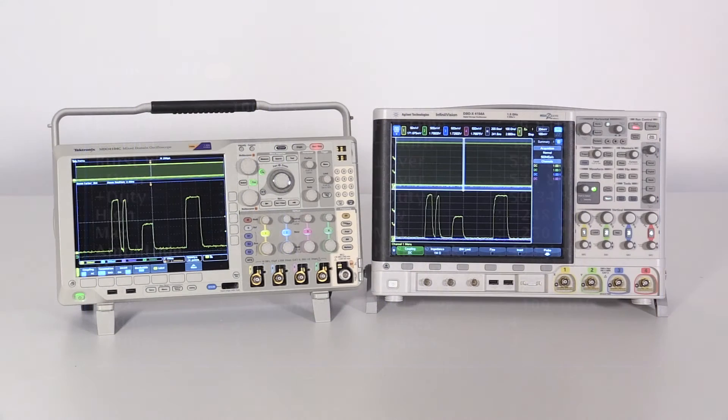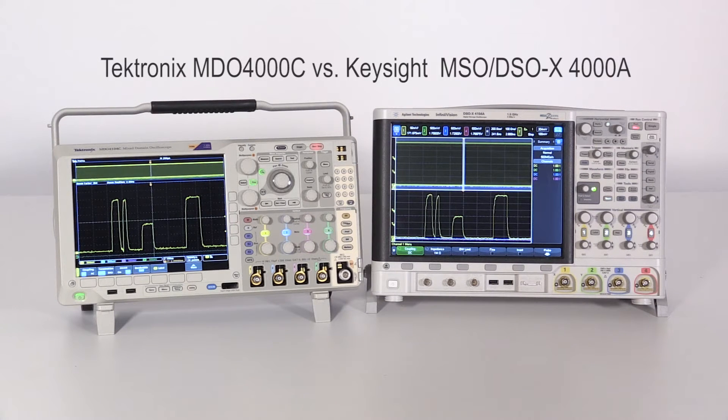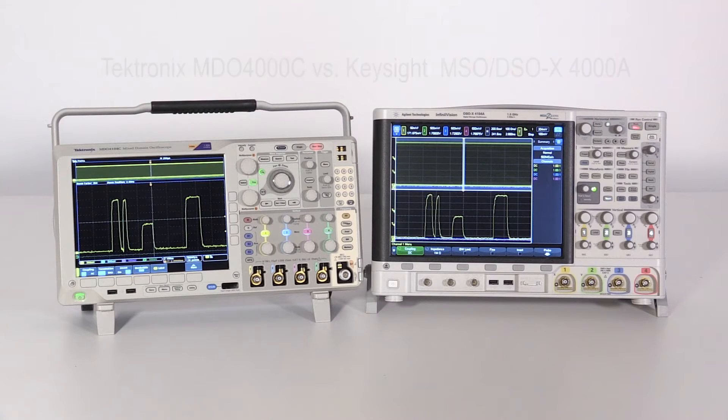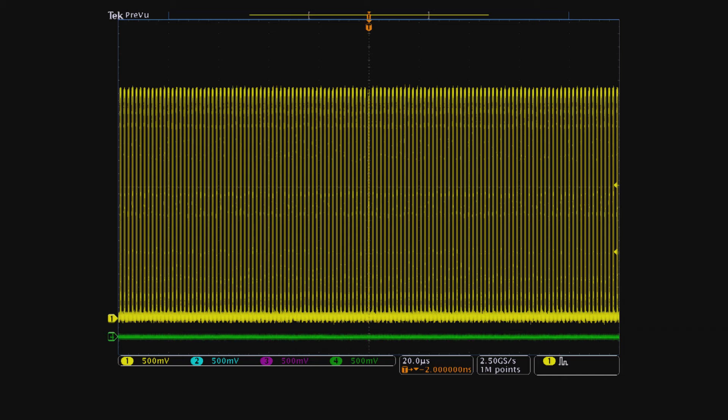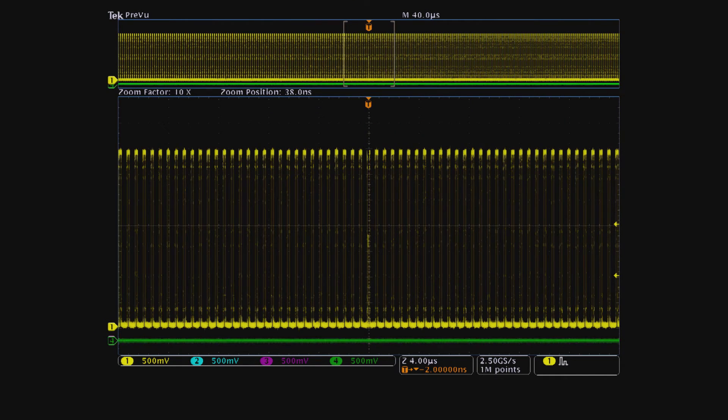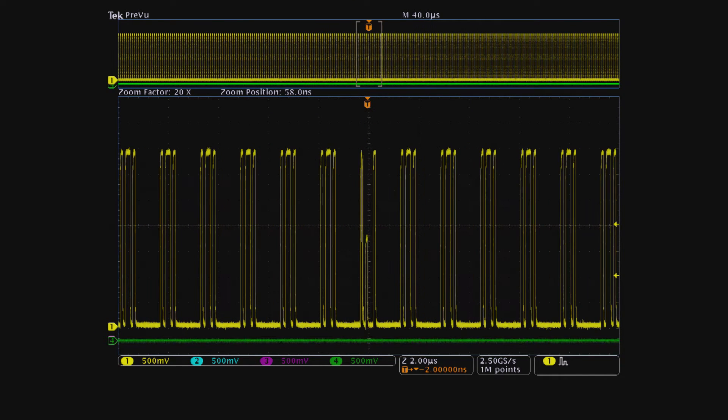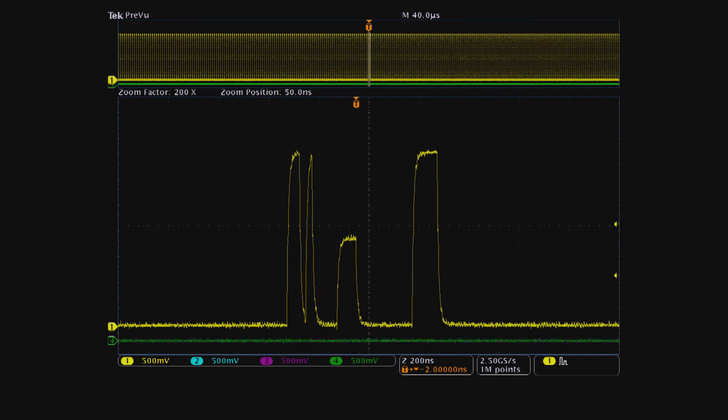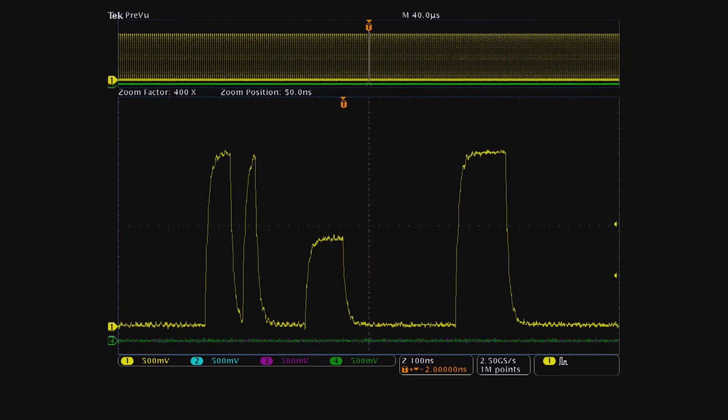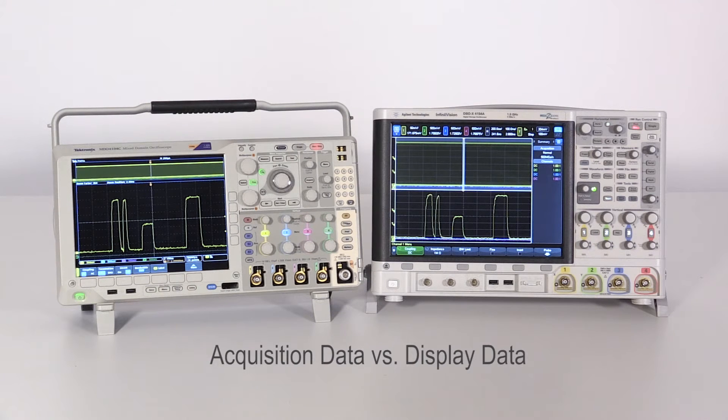Let's look at a comparison of the same waveform measurements performed on both the Tektronix MDO-4000C and the Keysight X-4000A. Both oscilloscopes acquire more data than the horizontal display resolution, therefore the acquired acquisition data is converted to display data before the waveform is shown on the oscilloscope display, but there is a difference in the way each scope handles measurements.